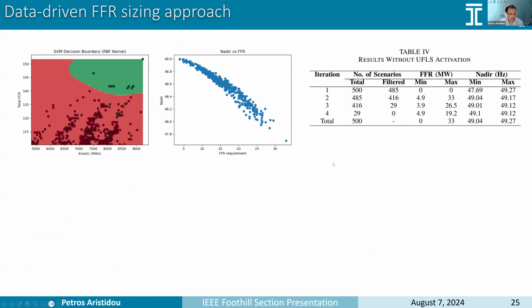We did that on the Cyprus system, and these were the initial scenarios that we had. The majority of them were not secure, with the post-fault nadir below 49 hertz. After 4 iterations, we ended up fixing all of these problems and estimating the required fast frequency reserves to be 33 megawatts. A nice result is also that the nadir and the fast frequency reserve have a more or less linear relationship here. So the lower the nadir, the higher the fast frequency reserve requirement.